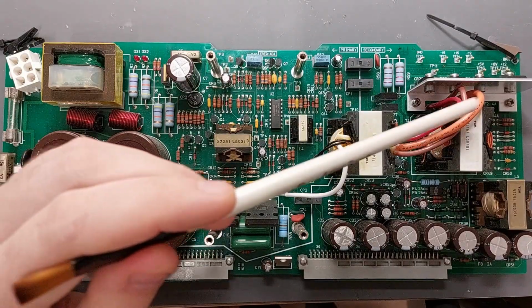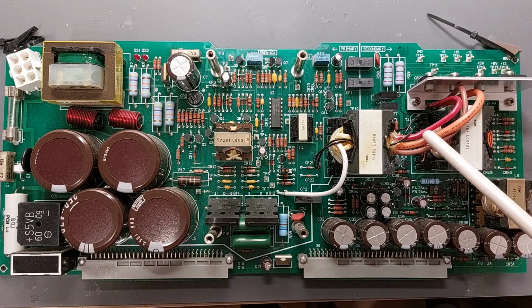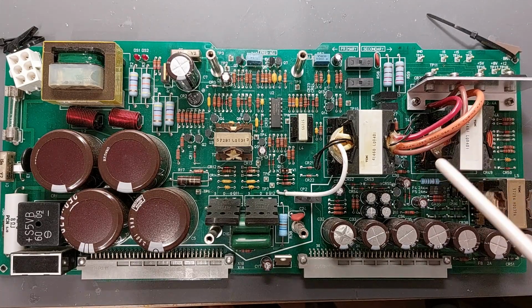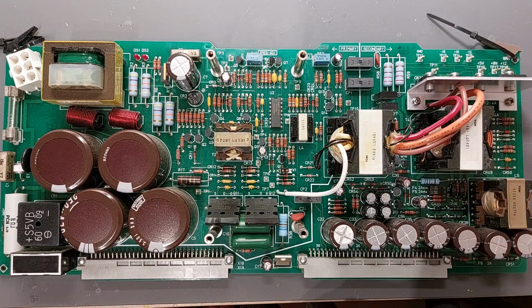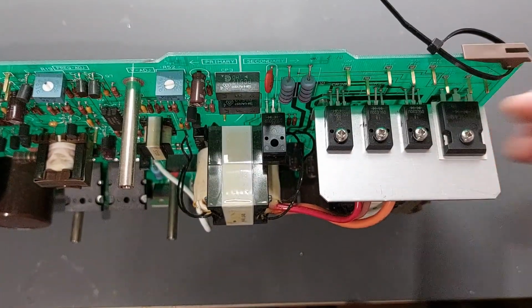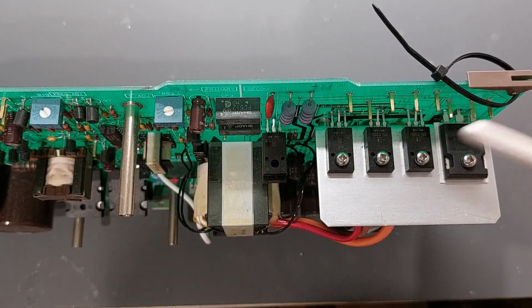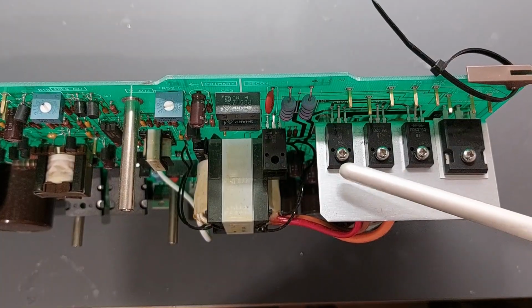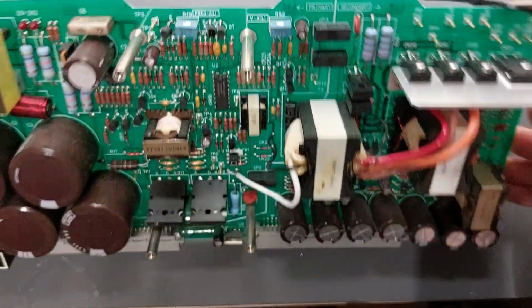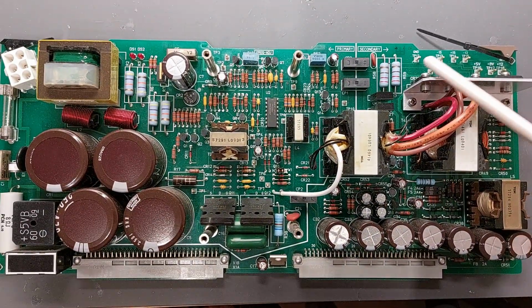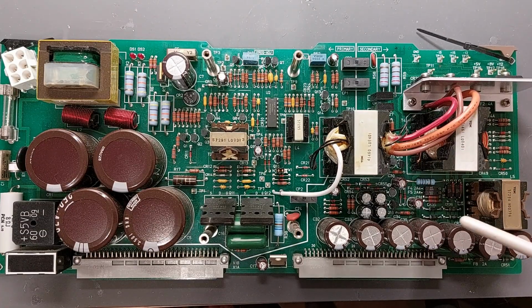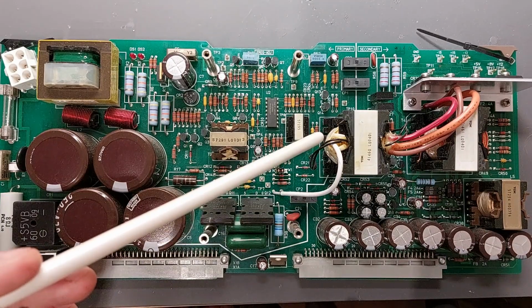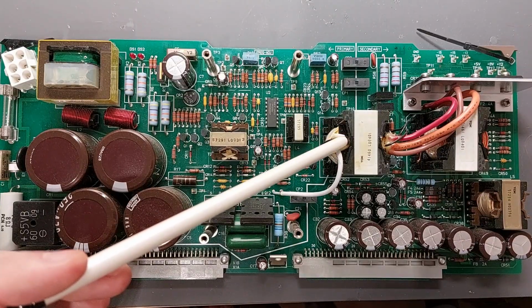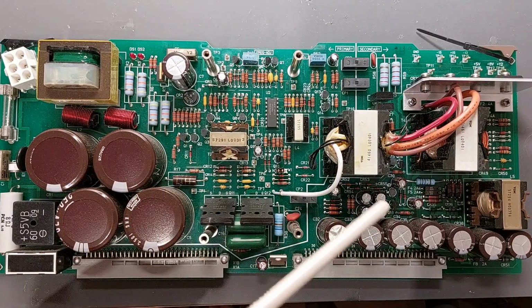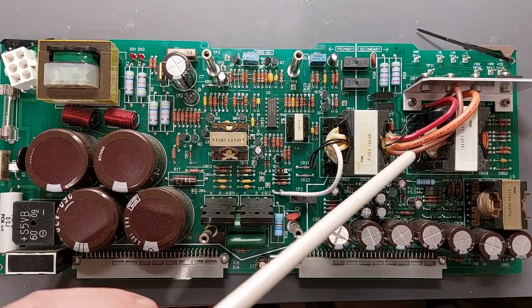Then we have the secondary windings coming from these here. This is another common mode filter, for the secondary winding this time. All of the secondaries except the plus 5 volt rail are going through this inductor filter, and the 5 volt rail has its own inductor here. On the final stage we have these bridge rectifiers. They are for the 5 volts, plus minus 12, plus minus 15, and that's basically everything that we have here. So the secondary voltages are completely not stabilized. The only feedback that we have is through this primary winding. That is why each board in this device has its own linear regulator, because these voltages are not controlled in any way here.